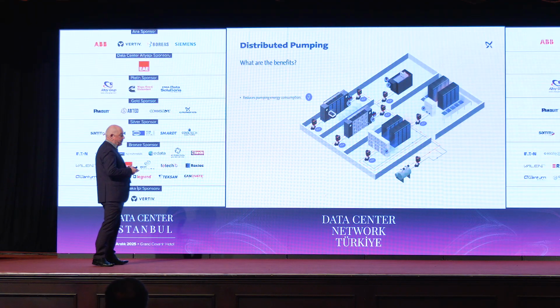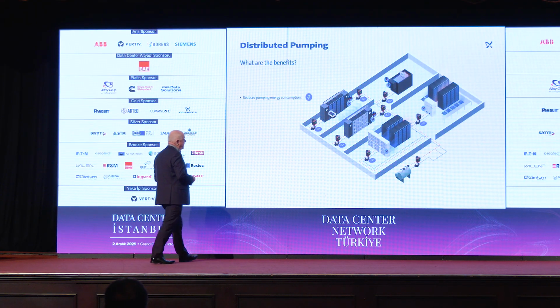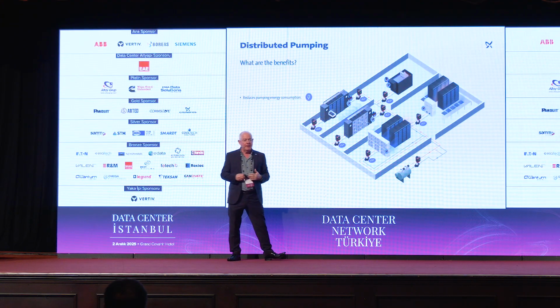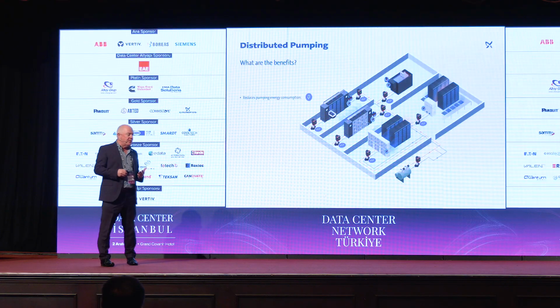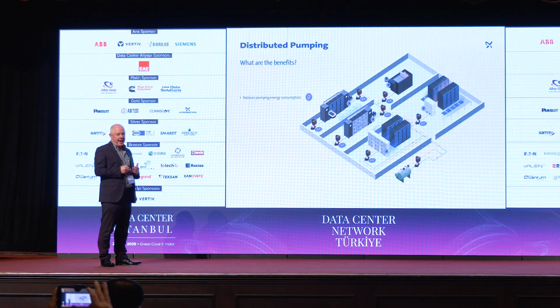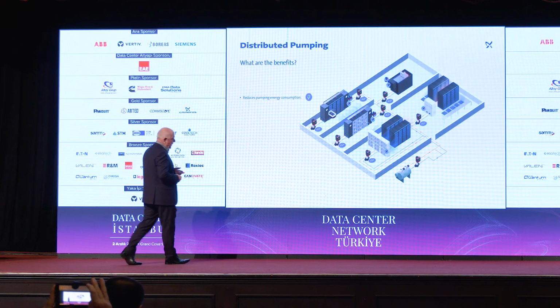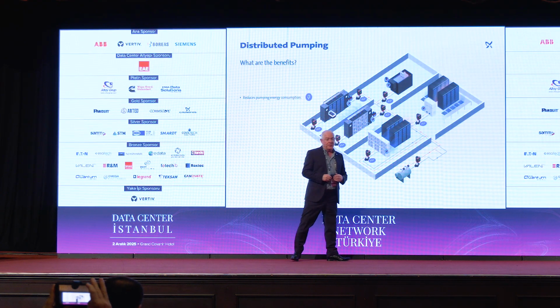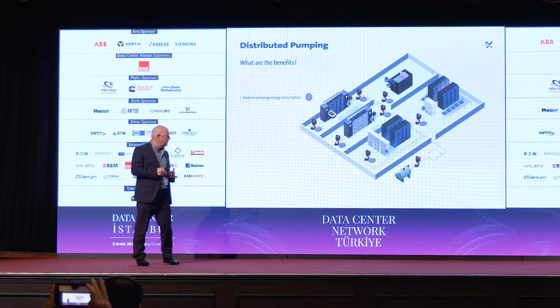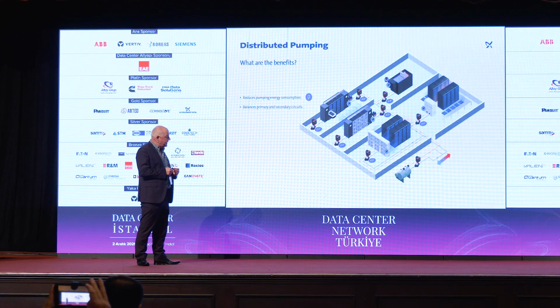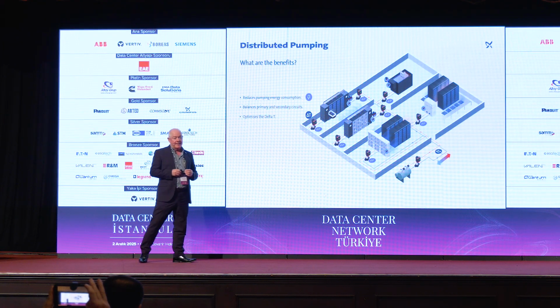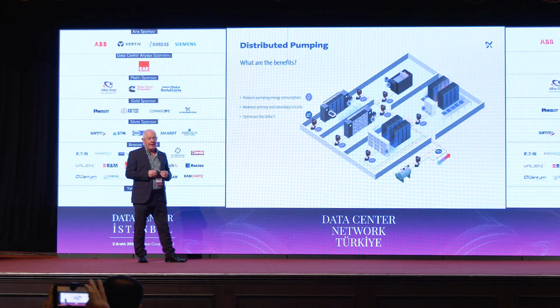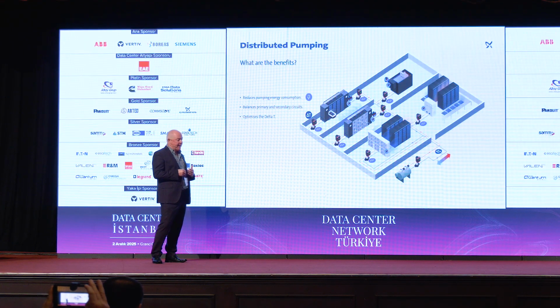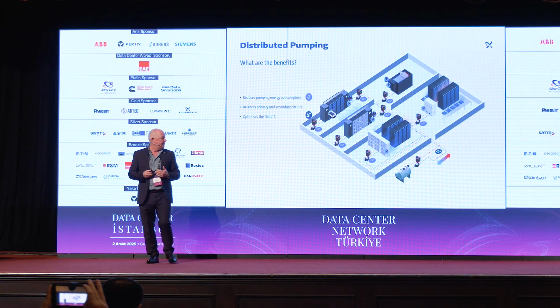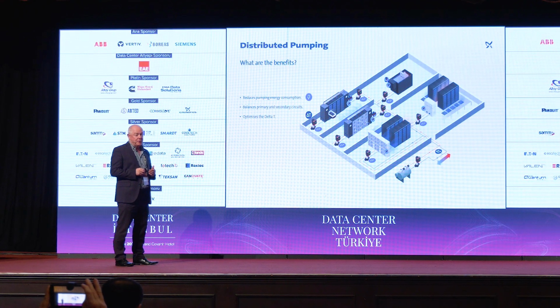And some of the other benefits, as I mentioned, it reduces the energy consumption on the pumping plant. So all of these pumps here will use less energy than a standard design of a pump system. We would estimate that in a lot of cases we can get up to 50% energy savings on the pumping plant. And we can also affect energy savings on the chiller plant as well, because we get the system very, very well balanced. As I said, we balance the primary and secondary, and we optimize the delta T. So whatever the delta T is designed for, we keep it at that. We won't have low delta T syndrome, and that gives us efficiency on the whole cooling system. And that efficiency, we've measured in some cases, can be up to about 14-15% on the cooling load, which is substantial.